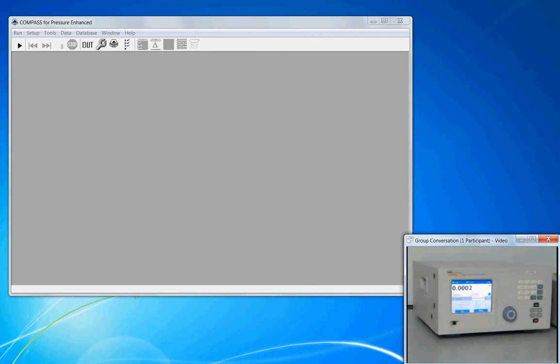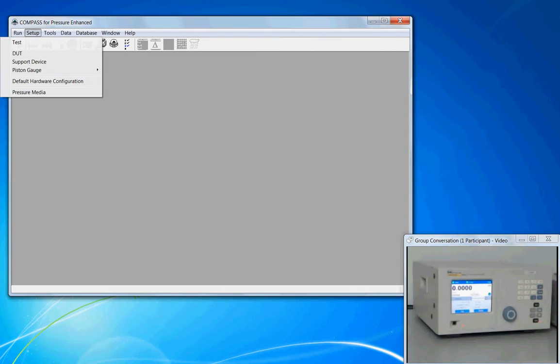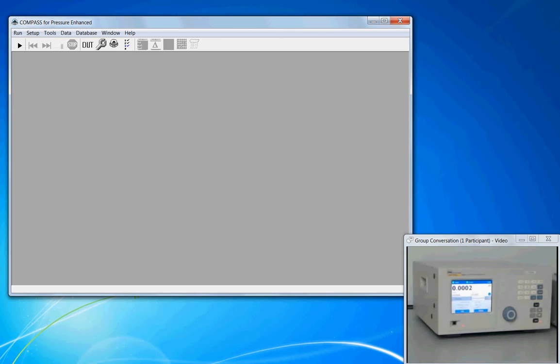The PPC-4 is configured as a support device. To use it in the calibration, we first have to create a support device definition. We can access this through the menu bar, Setup, Support Device, or we can go directly to the toolbar and click on the Edit Support Device button.